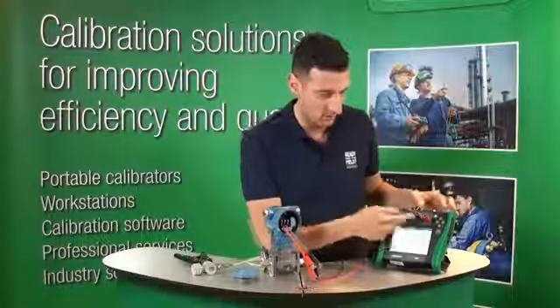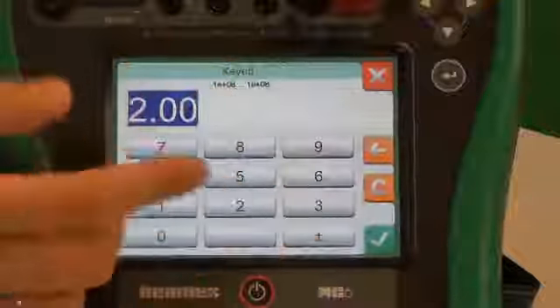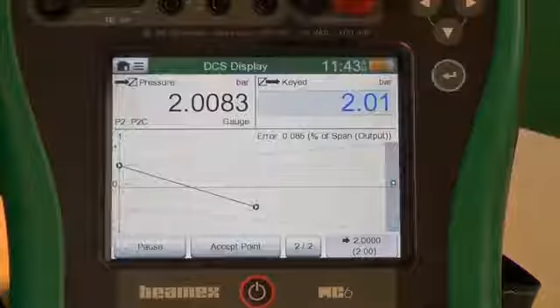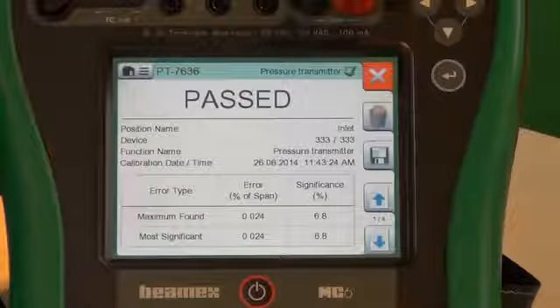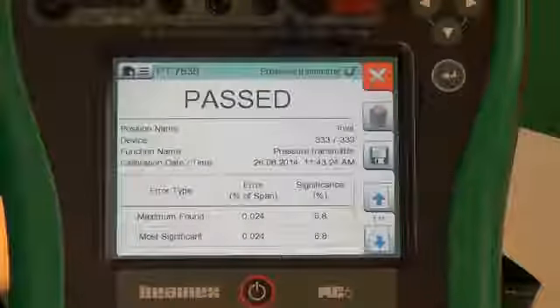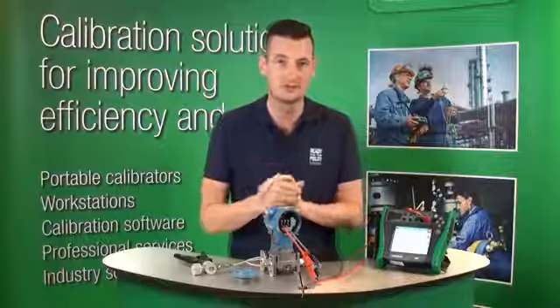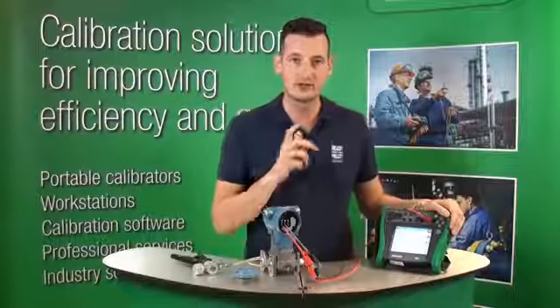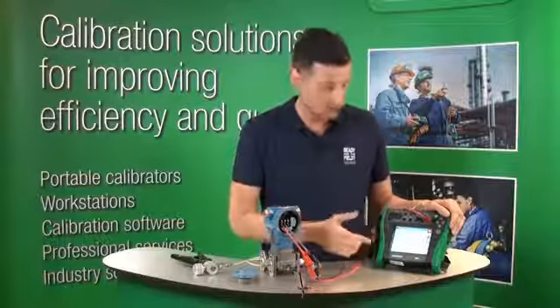We'll call our guys in the control room, and they'll tell us the pressure they can see on the screen. We accept that point, and that's how we calibrate both the pressure transmitter and the control room display at the same time.